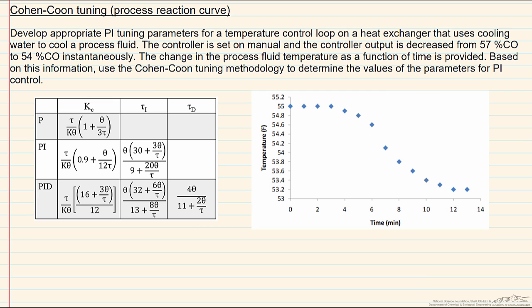Based on this information from this test, how can we develop appropriate parameters for PI control using the Cohen-Coon tuning methodology? So Cohen-Coon is one of many types of tuning parameter correlations that is based on open loop testing, and an open loop test is what we have just described earlier, which is basically the controller being on manual and an adjustment being made to that controller.